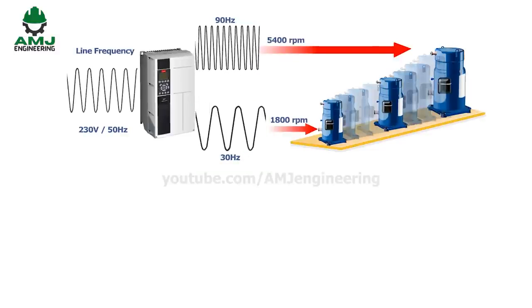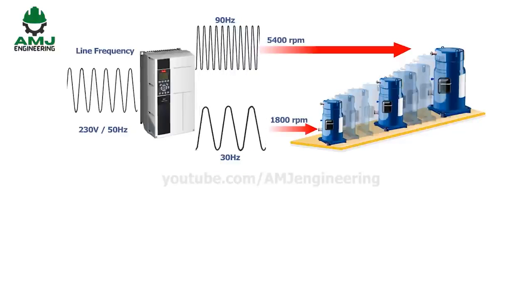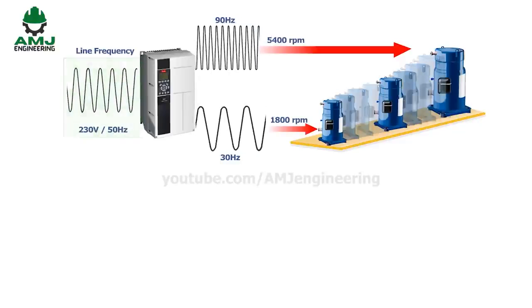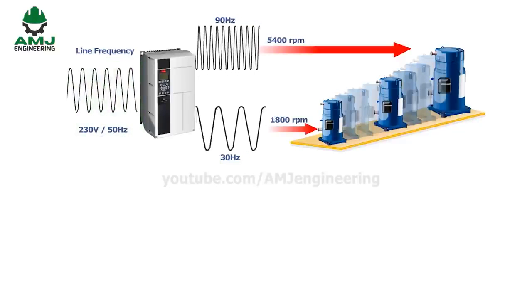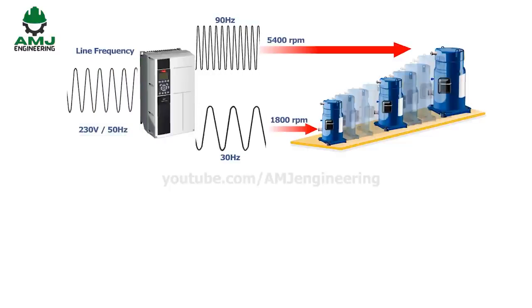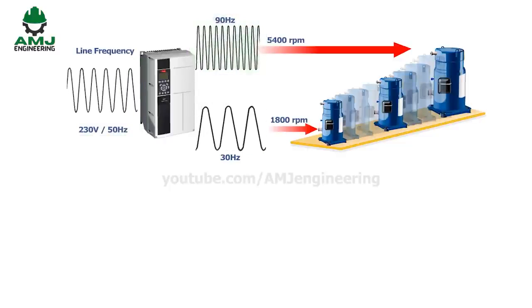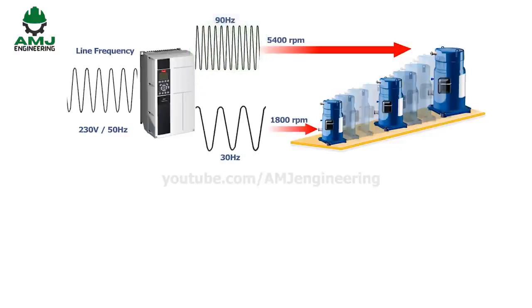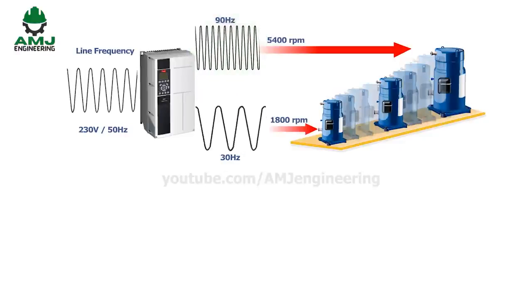To run the compressor at a higher frequency than the power supply frequency of 230 volts 50 Hz, it is necessary to supply higher voltage to the motor. For 90 Hz frequency we need to supply a higher voltage to the motor, which is calculated as follows.